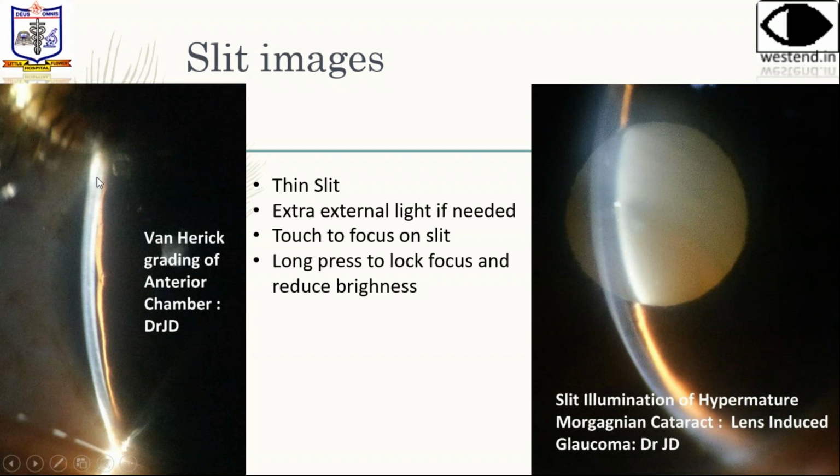You need to, one, focus on the slit, and two, give extra background illumination, which can be done with another smartphone with the flash on, if you want to do everything by smartphone, or if you have a flashlight, you can use that. Once you have the extra illumination, this photograph would have turned out better, with the details on the sides visible, with the slit also visible.